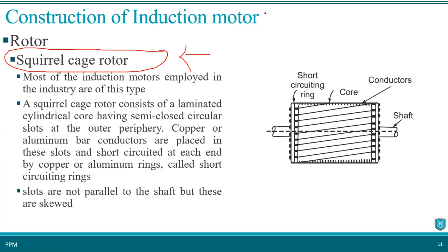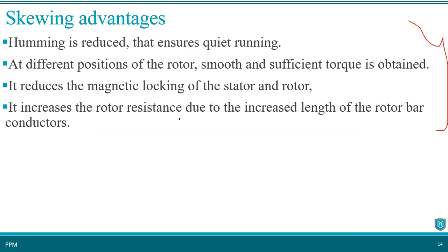In the squirrel cage rotor, we put bars on the rotor. They will be either of aluminum or of copper material. These bars are shorted at the end with the help of end rings. That is also important. As it has a construction like a cage, it is named a squirrel cage rotor. Second, these bars are skewed at a certain angle, so they are not placed horizontally. They can reduce the humming, and there are more advantages. So it can be an important descriptive or MCQ question: what is the significance of skewing?